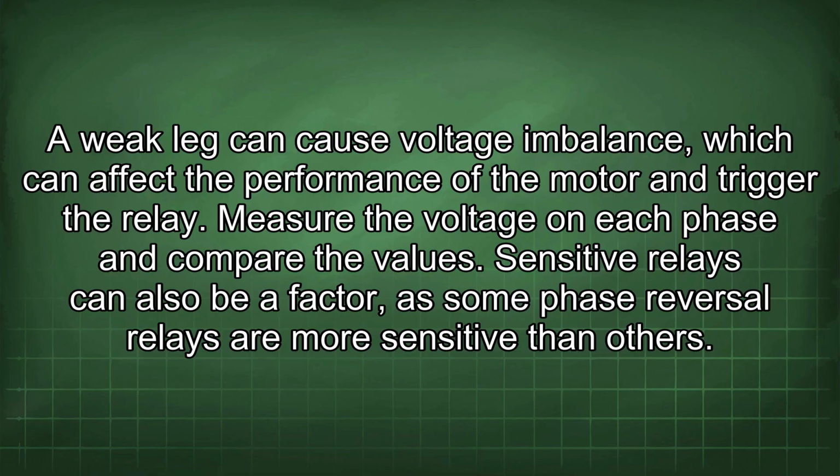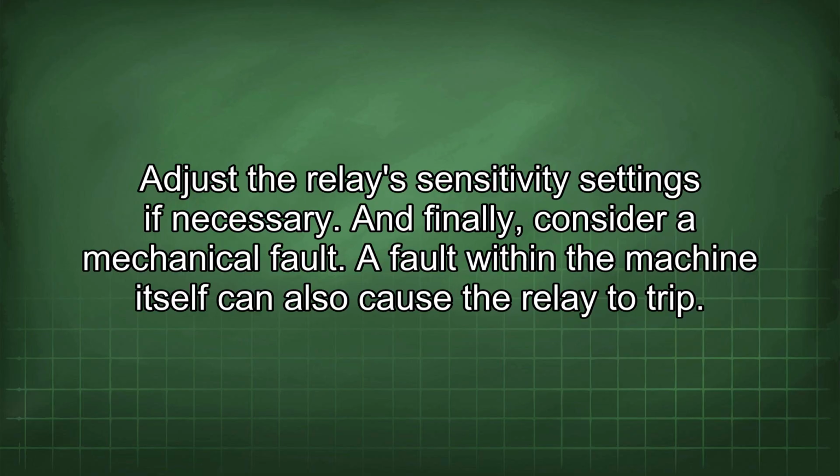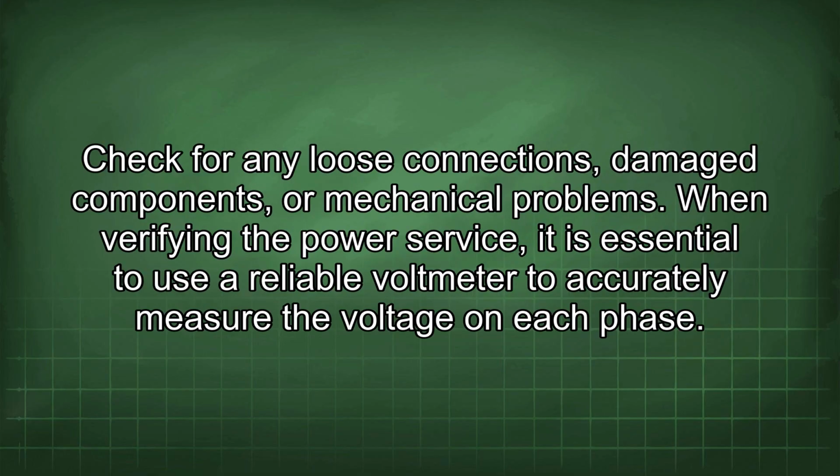Sensitive relays can also be a factor, as some phase reversal relays are more sensitive than others. Adjust the relay sensitivity settings if necessary. And finally, consider a mechanical fault. A fault within the machine itself can also cause a relay to trip. Check for any loose connections, damaged components, or mechanical problems.